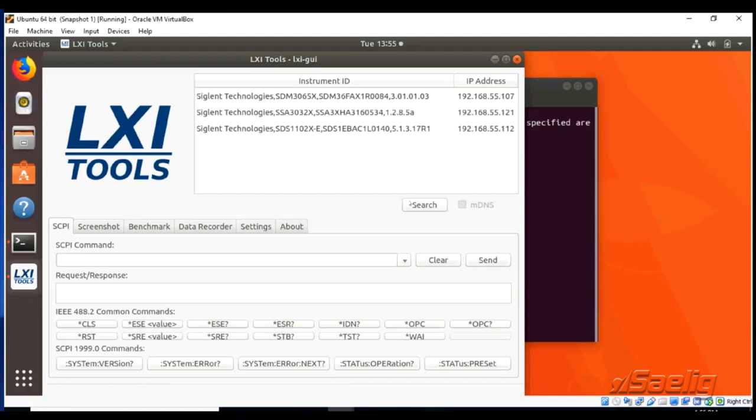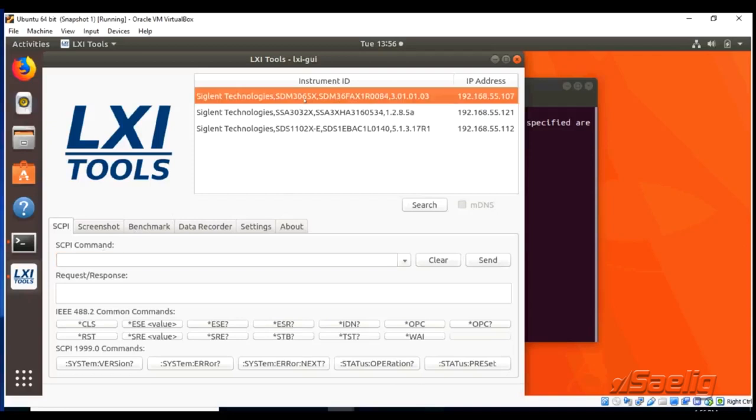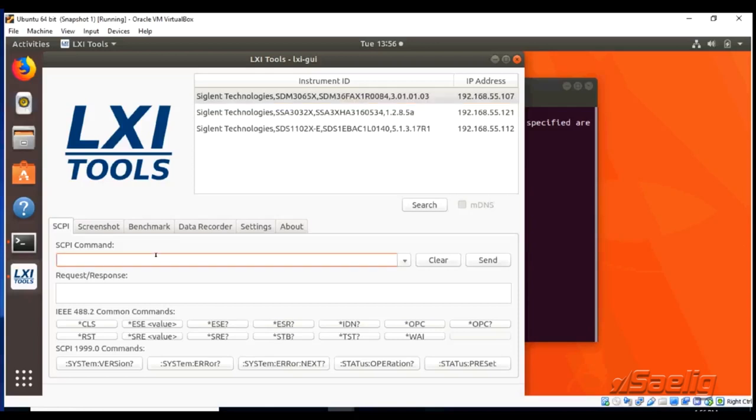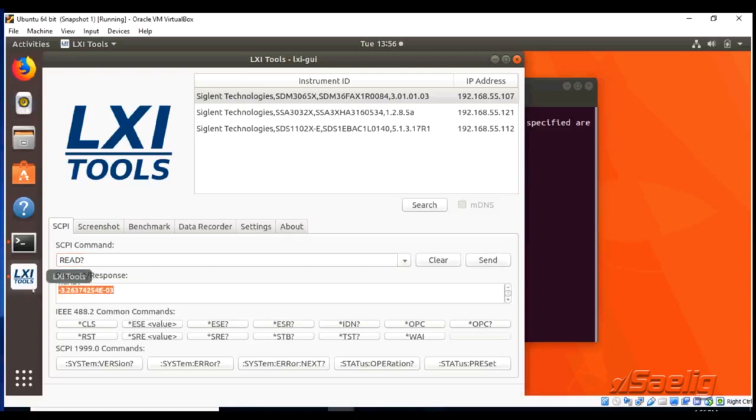We've got a command line for the SCPI. We did the Discover as we did earlier and now we have all of the instruments and we'll simply click on the instrument we want to control and then we'll go down to the SCPI command line. We'll type in read as we did previously for the multimeter. We'll finish it with a question mark and now we'll get that same reading here in the SCPI window.